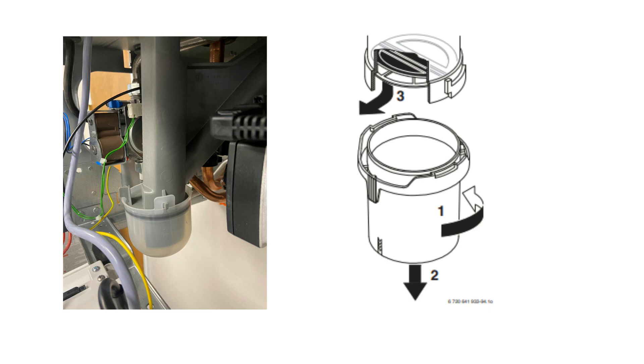Clean the condensate trap and remove the diaphragm at fan inlet connection and check for contamination or cracks. Replace the diaphragm if defective and set parameter 5.B in the first level service functions to 12. Check heat exchanger for soil and clean following the detailed instructions in the installation manual.